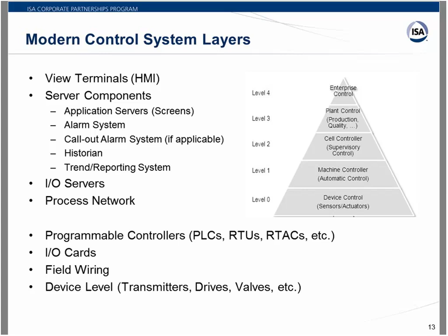If we first go to the I/O level, these are the panels that you typically see in a plant or a platform or a site. You'll have your hardwired I/O, you'll have digital inputs and outputs, you'll have analog inputs and outputs, voltages, currents, contact types. These details have to be sorted out. On some systems, particularly on the DCS side, you'll see fieldbus. So you'll see Profibus or Foundation Fieldbus or AS-i Bus, and HART is used in a lot of these systems. And you'll have network connectivity to some devices. Some devices, say a process analyzer, may have a network connection that goes directly into a controller.